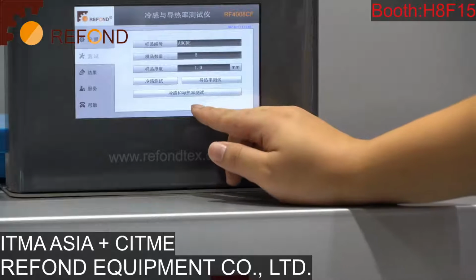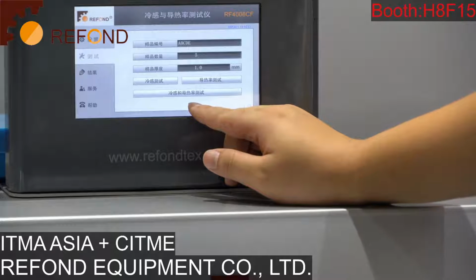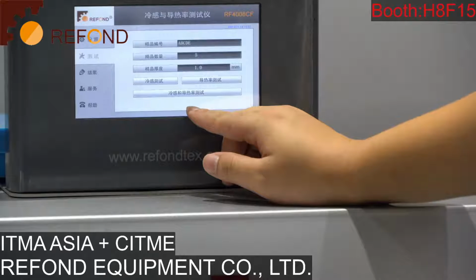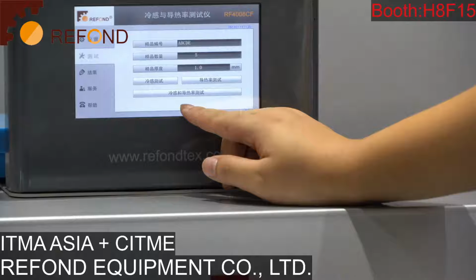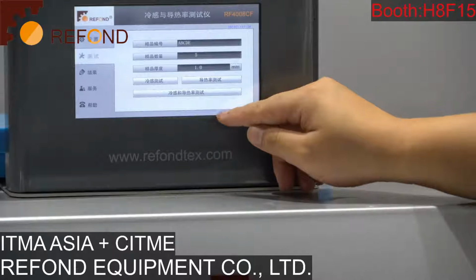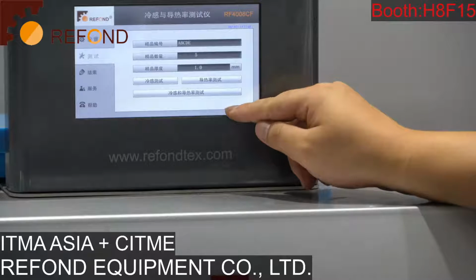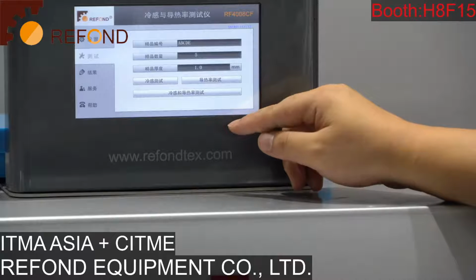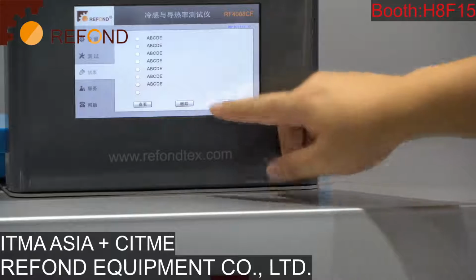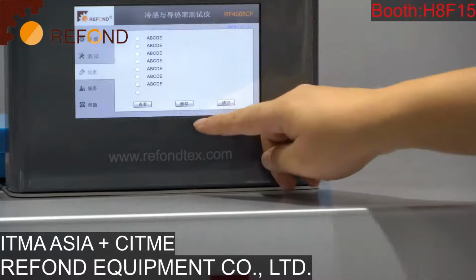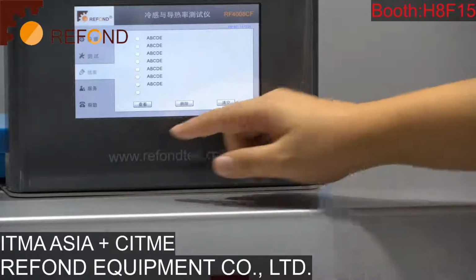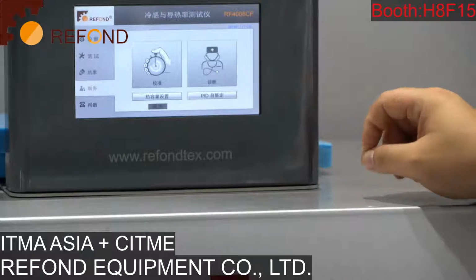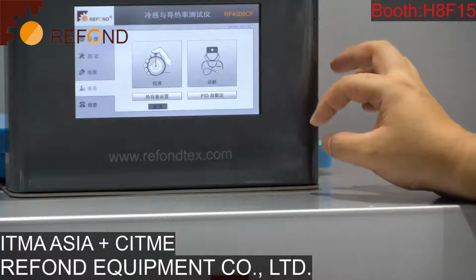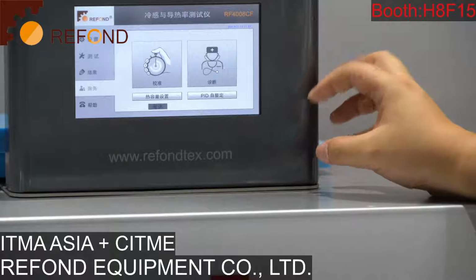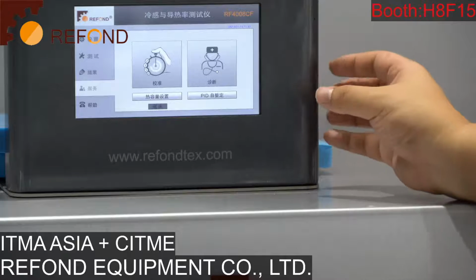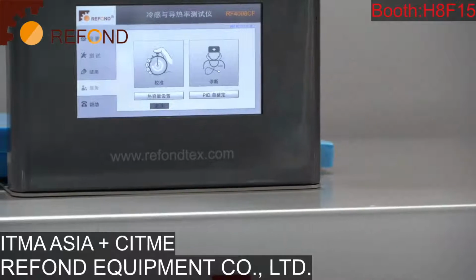If you choose the last one, which will do the 2 tests together, the machine will automatically adjust the temperature and then do the cool feeling test first. Then the test head of the cool feeling test will move away, and then the test head for the heat conductivity test will come into place for the measuring of the data. You can see all the stored results in the result tab and then view the detail inside. In the service page, you can do calibration for all the temperatures and the powers and the values related in this machine. Everything can be calibrated, so the traceability is very good.